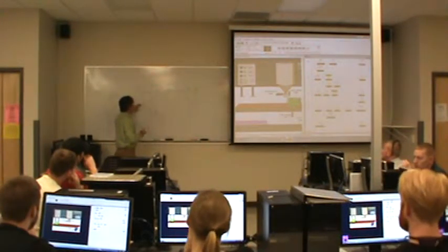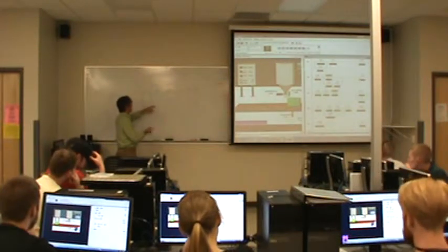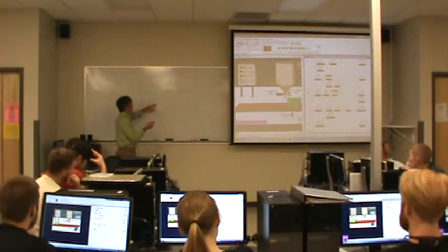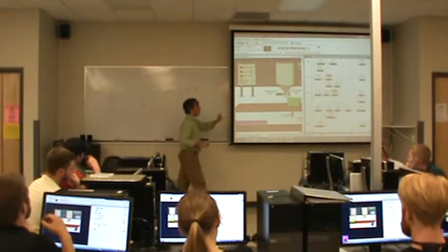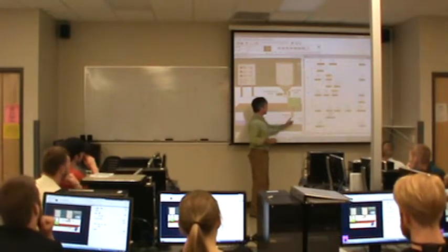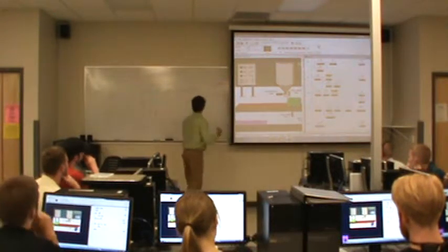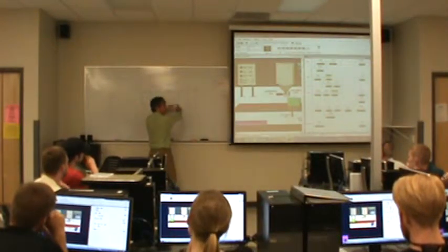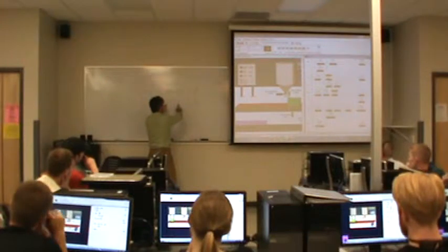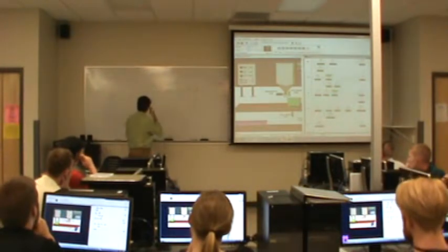So anyway, if the full bit is off, prox sensor true, level sensor not true, we know we're not in this condition because we're going to remember the condition where we've got a full box, right? But we don't have a full box, so it's okay to go ahead and fill it with the motor off. Okay? We'll turn on the fill lamp, and that makes sense.